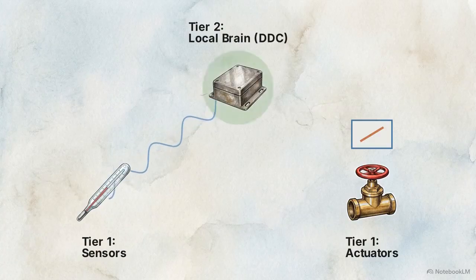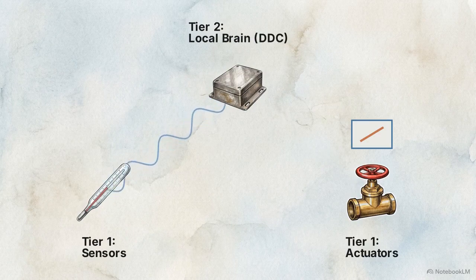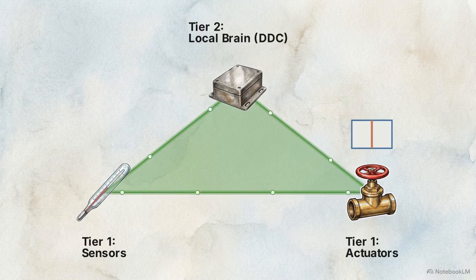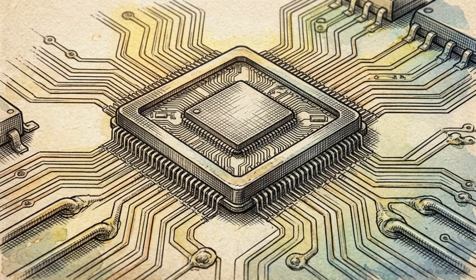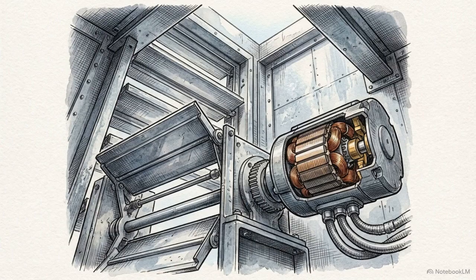Connecting these two components requires Tier 2, the Direct Digital Controller. This hardware acts as a local brain for a specific physical zone. DDCs run localized logic loops. They constantly ingest the raw data wave from the sensors, run it through pre-programmed algorithms, and fire immediate commands back down to the actuators to maintain a precise set point.